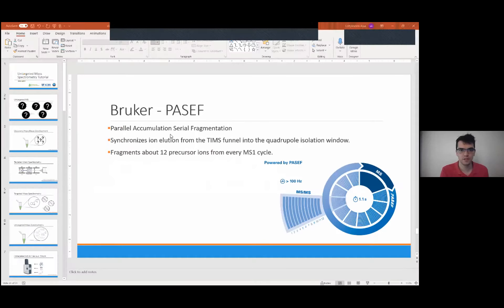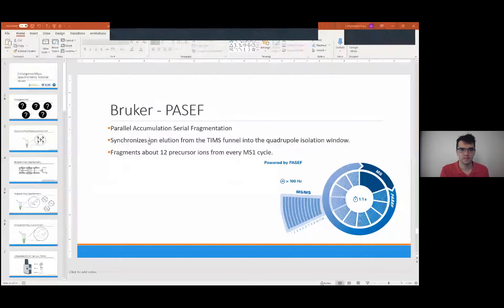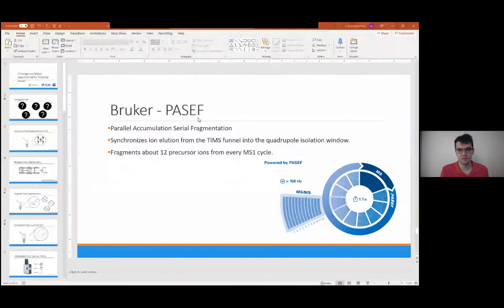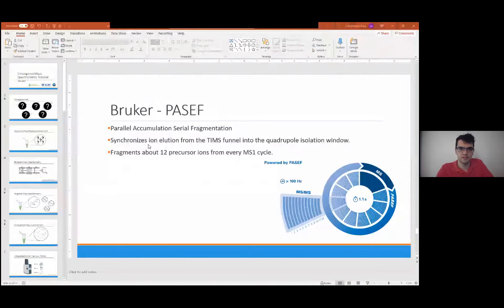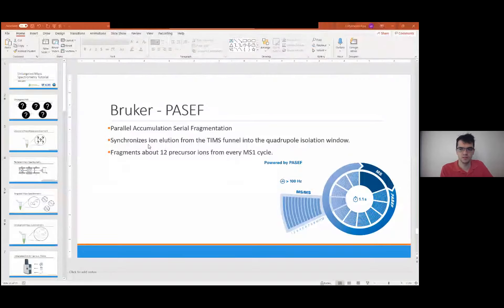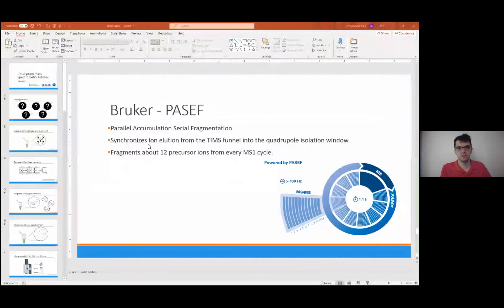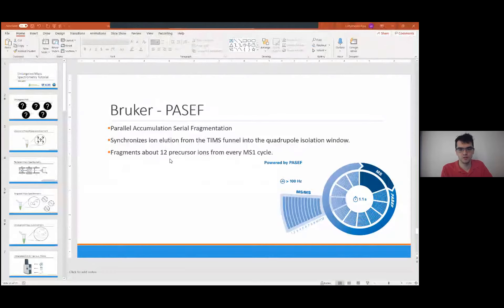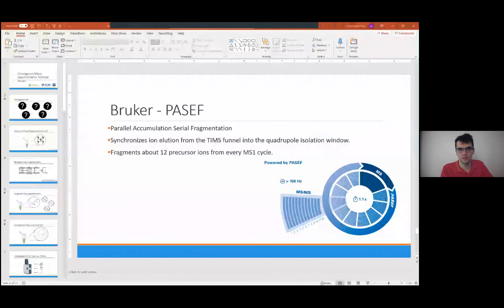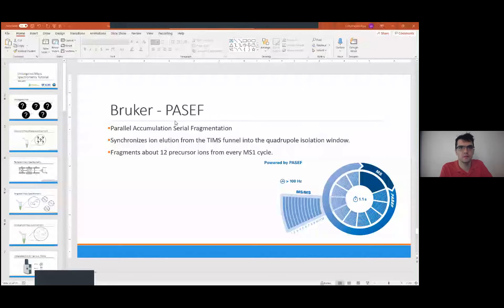I realized after making this video that I should have had a slide on it, so I just put one together really quick. So PASEF is a system that is patented and made by Bruker. It's parallel accumulation and serial fragmentation. It's a synchronization between the TIMS funnels and the quadrupole. So ions are accumulated in the trapped ion mobility system and then selectively released into the quadrupole. So that lets you fragment many precursor ions more than you would usually get, so about 12 in this case, I think, per MS cycle. And then you go across multiple MS cycles and you get many ions. Yeah. So it's just a different type of fragmentation method. Yeah. And we don't over-inject. We actually control the amount of samples we actually put in.